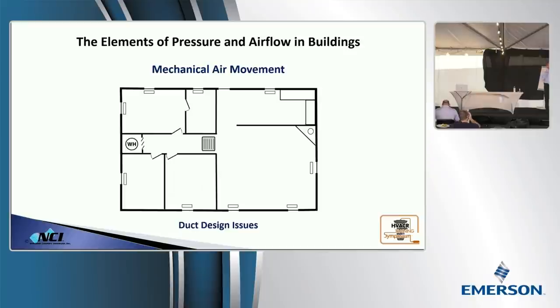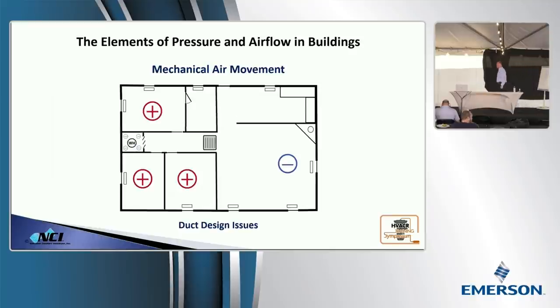But something's variable here. Something can change. What is it? We've got doors or conditioned space manual dampers. Customers come home. They start living in the duct system. They start to change these damper positions, and things happen. When you close a door to a room that has a supply register only to it or that has air balancing issues, you're going to change the pressure because now you have cut off any communication with the rest of the building. And air always takes the path of least resistance.